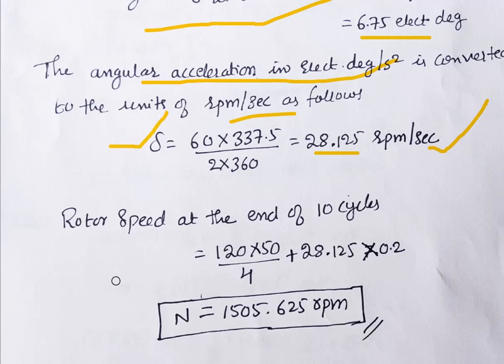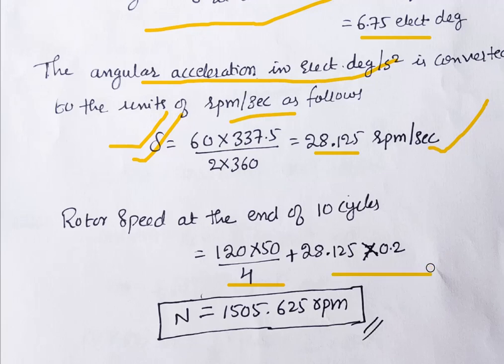The rotor speed at the end of 10 cycles (0.2 seconds) is: N = synchronous speed + acceleration × time = (120 × 50 / 4) + (28.125 × 0.2) = 1500 + 5.625 = 1505.625 rpm. This means the rotor speed increased by approximately 5.625 rpm due to the imbalance between mechanical input and electrical output.